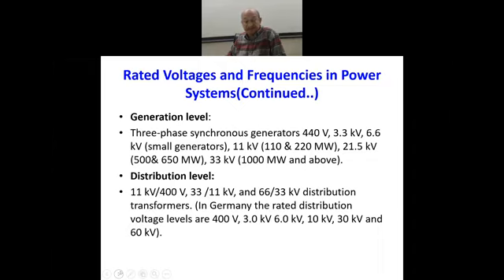And still larger, but rare, 1000 megawatt generators have their power generation voltage level to the tune of 33 kV. It is difficult to provide insulation within the windings of the generator for higher voltages, and that limits the voltage level at which the power is generated in power generating machines or synchronous generators.